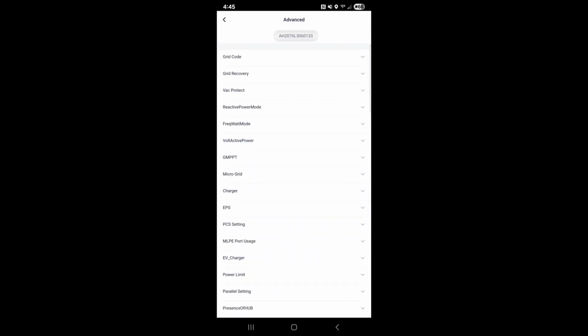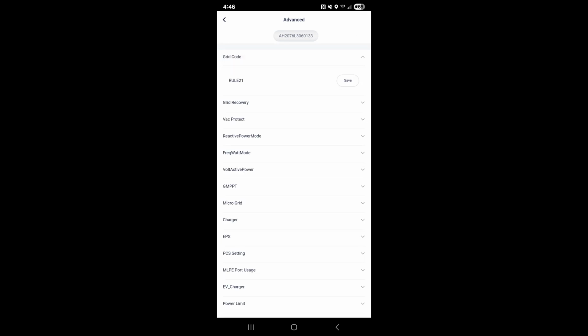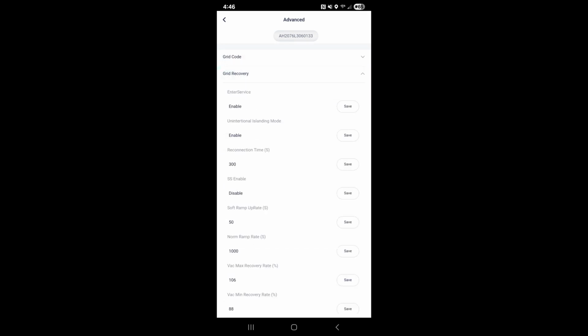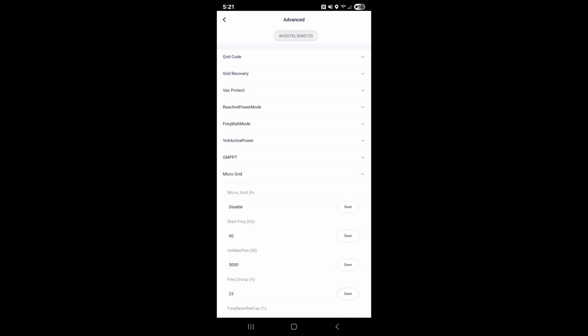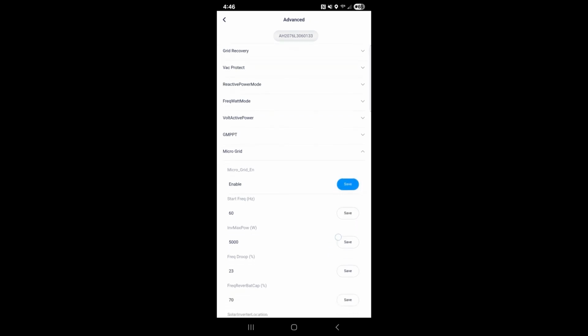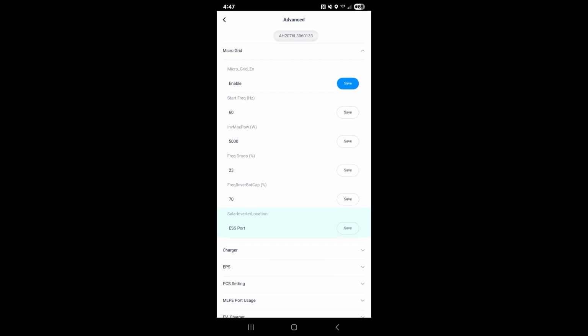Once in the advanced settings, select Grid Code and choose the code appropriate for your location. Select Grid Recovery and confirm Enter Service shows enabled. Next, select Microgrid and change this to enabled. Then press Save. Confirm the solar inverter location from this same list. If your AC-coupled PV system is landed in the Q.HOME Hub busbar on a dedicated circuit breaker, choose ESS port. Change this to backup port when the AC-coupled PV system is landed on a circuit breaker on the panel connected to the load terminals on the Q.HOME Hub.